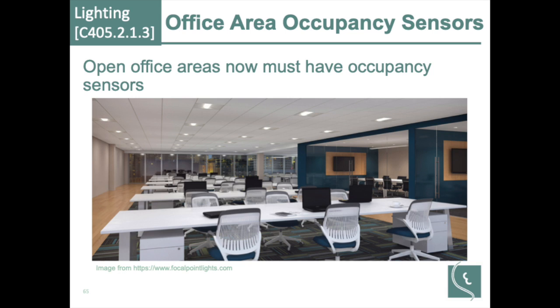So like in that example, if somebody walked into that room and only sat in the very front row, only light those lights. Then if these were tied, in code minimum, if someone came in and sat in this chair, the lights that are directly over this zone of 600 feet can go to 100%. All the remaining could go to 20%. Because at least one zone has been occupied, so all of them can go to at least 20%. So that you automatically kick the whole room. The whole, correct. The zones must be limited to 600 feet.